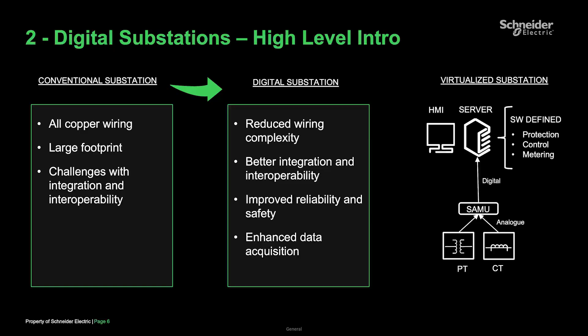Improved reliability, so less dependency on human operation and safety. A lot of substations today are using Modbus protocol, so protocols that are not super cyber secure. Now, when we move into IEC 61850, it's a much more secure environment from a cybersecurity perspective. And then enhanced data acquisition, since more IEDs will be accessing those samples from the merging unit.